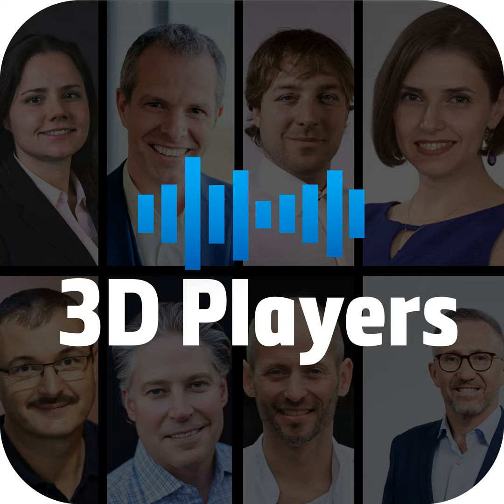For things like anatomic models and surgical guides that are tied to a surgical plan, those things in the US are class 2 devices that would require a 510(k) to be submitted prior to marketing those devices.